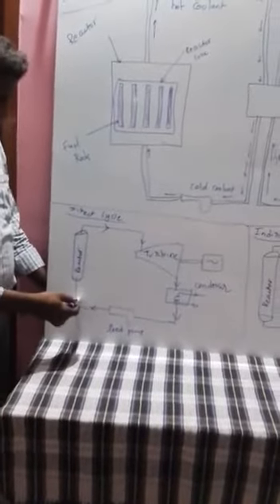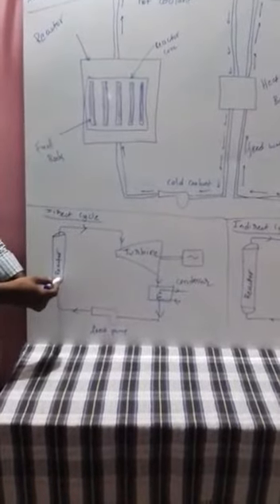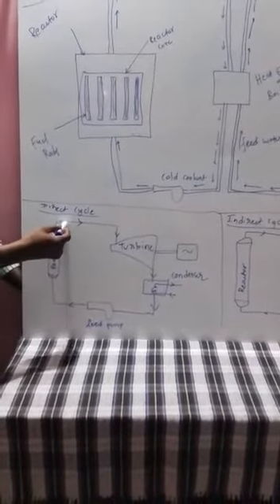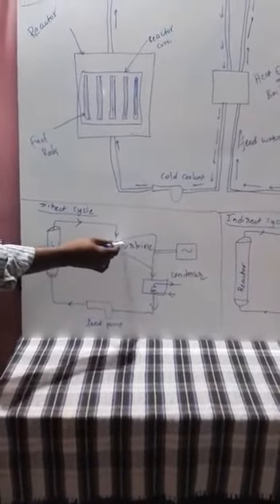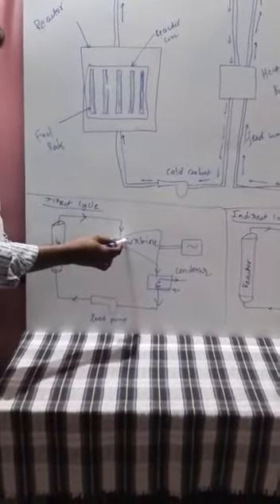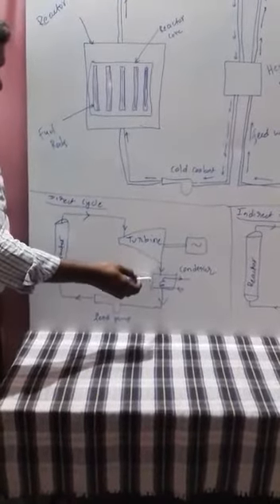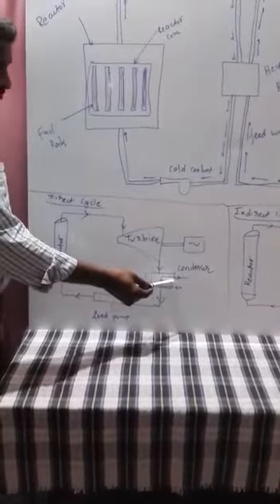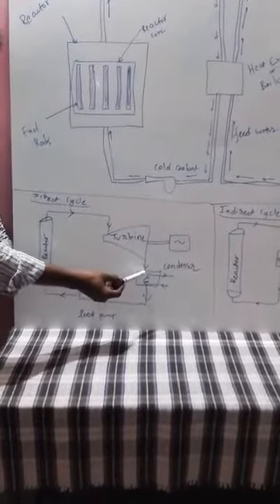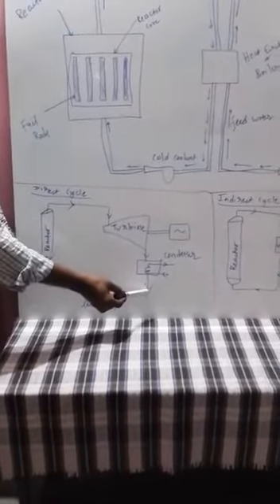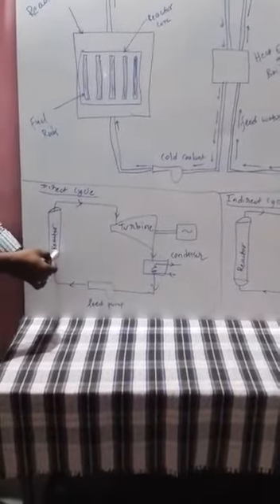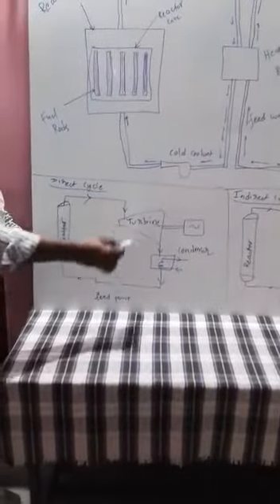The working fluid, which is water, is pumped by the feed pump and enters the nuclear reactor directly. There, the water absorbs the heat and steam is formed. This high-energy steam enters the turbine and produces work as it expands over the turbine blades. The low-pressure, low-temperature steam then enters the condenser, where it rejects the latent heat of condensation to the circulating cooling water. The steam condenses into liquid, called condensate, which enters the feed pump and is pumped back to the reactor, completing the cycle.